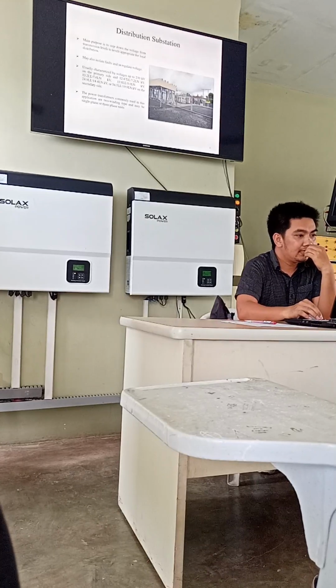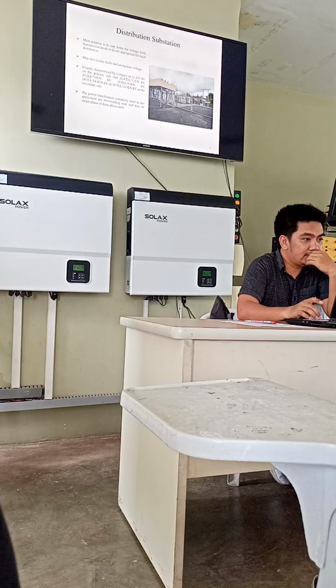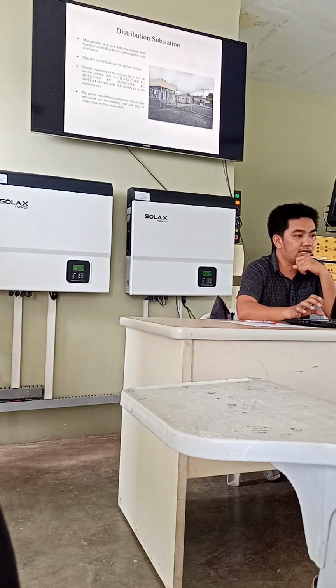And the distribution substations are stepping down from the subtransmission level to the distribution voltage level. So the typical or usual voltage used for the primary side of the distribution system is 12.47 line to line, and 7.2 line to neutral. 13.2 line to line, 7.6 line to neutral. 13.8, this is the usual. Sipalco is 34.5, and some ECs use 13.8 and 8 line to neutral. So these are common.